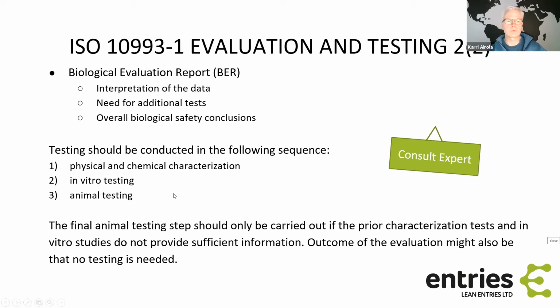And it's also making the overall biological safety conclusions, and suggesting, for example, some additional testing. This standard quite clearly states that all the additional testing should be conducted in the following order. First, do some more physical and chemical characterization, but if that is assessed as not bringing you any new information, then apply in vitro testing in the laboratory, in a Petri dish, a test tube, whatsoever. And then eventually, if you can't avoid any animal testing, then that is a choice.